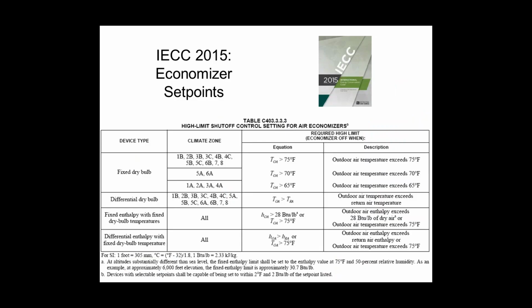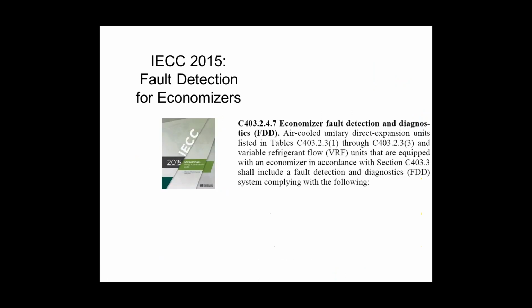All right, from a code perspective, this is the specific table that applies to us. We are climate zone 5A in Illinois, 6A for the southern Wisconsin folks we were talking about. So like I said, the cutover point is 70 degrees now, which is higher than it used to be if you have a dry bulb. If you have an enthalpy, it's 28 BTUs per pound of dry air and a 75-degree cutoff that you would use. And then differential enthalpy, it's basically whichever one's better, return air or outside air. And then you also have a hard cutoff on the outside air. So that table is the same as it's always been, just the numbers have gone higher to increase the amount of economizer days that we run.